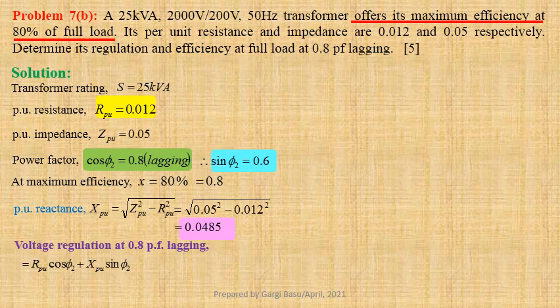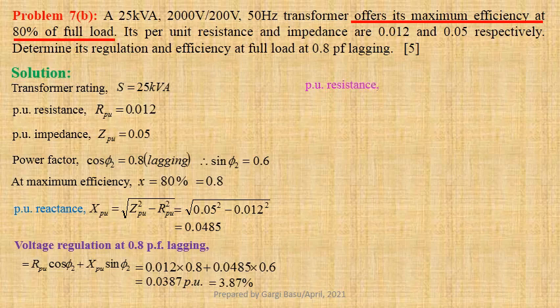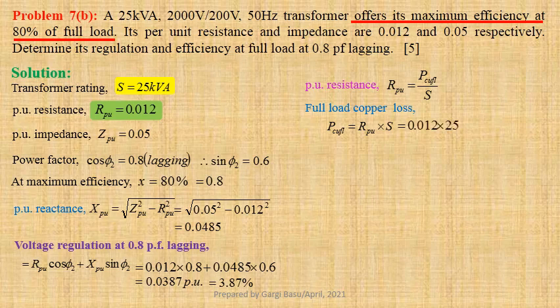Using values we get 0.012 into 0.8 plus 0.0485 into 0.6, that gives us 0.0387 per unit or 3.87%. Expression for per unit resistance: R per unit equals P copper FL by S. Therefore, expression for full load copper loss will be P copper FL equals R per unit into S. Using values we get 0.012 into 25, that gives us 0.3 kilowatt.